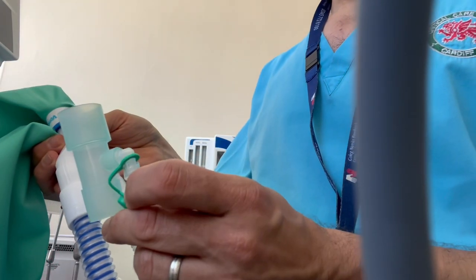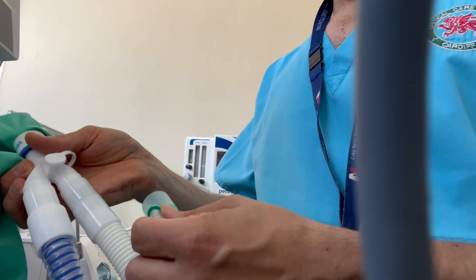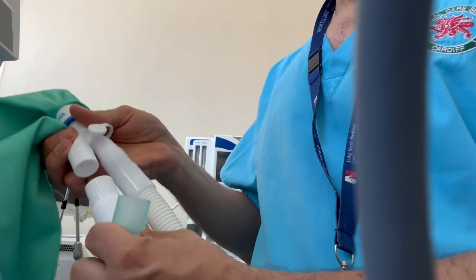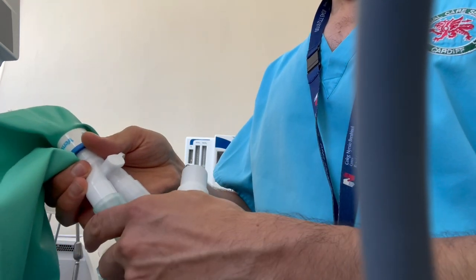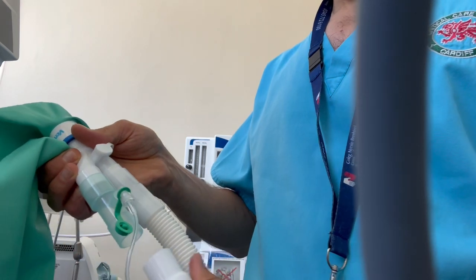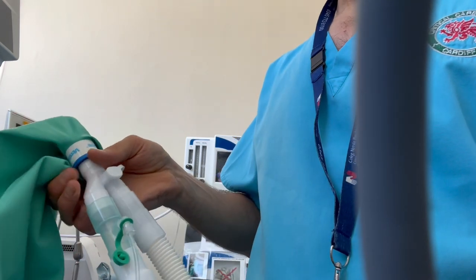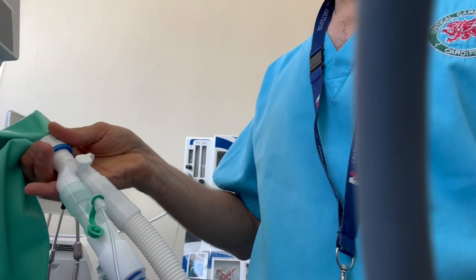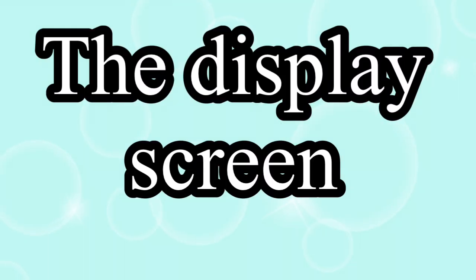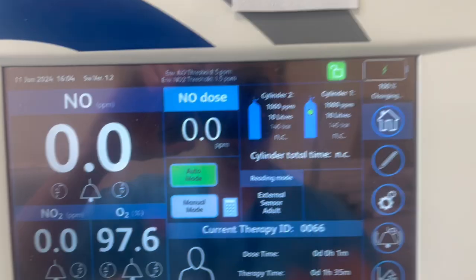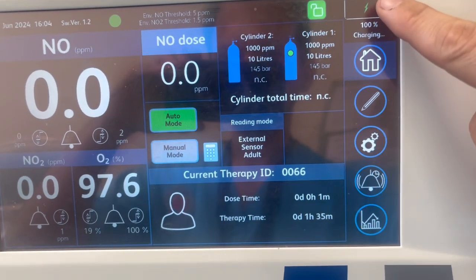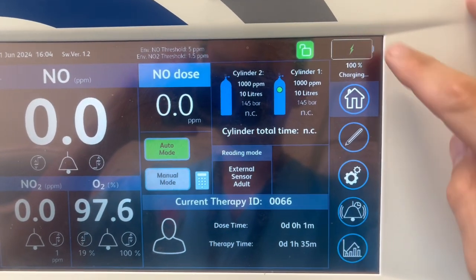The green sample line adapter can now be placed in the inspiratory side of the circuit, the blue side. The sample line connection should be facing upright to avoid water accumulation. We can see the display screen. We can see the unit is charging and how much it's charged.